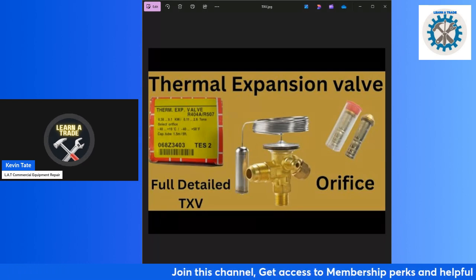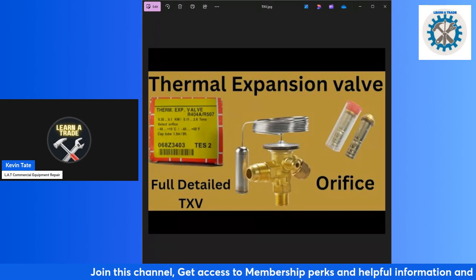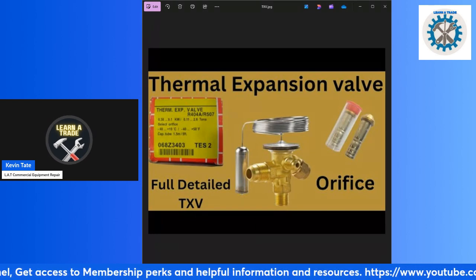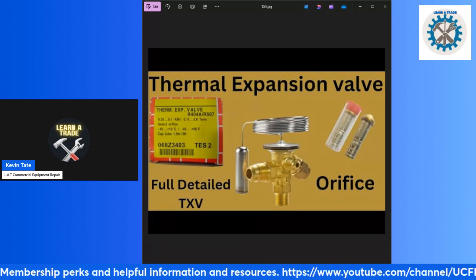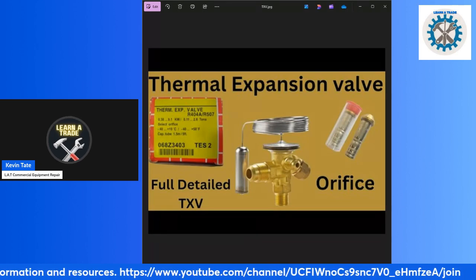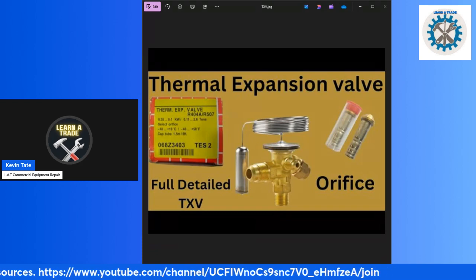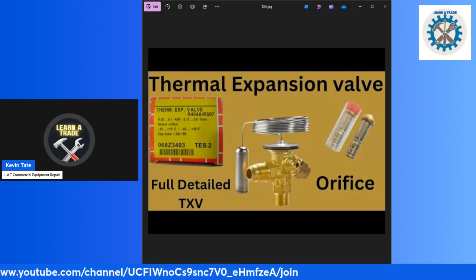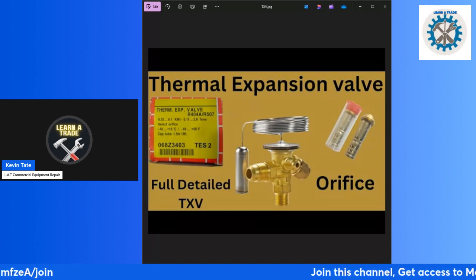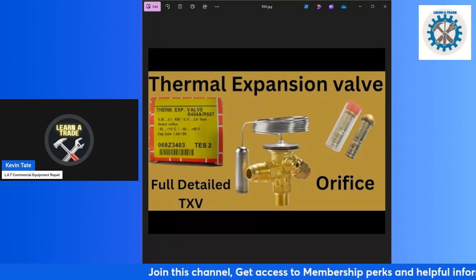Then go to the left to select the nominal tonnage rated valve. That's going to be the valve that you're going to select. You may have to recalculate the flow rate in tons using the liquid correction factor table if the actual liquid temperature is different from 100 degrees Fahrenheit used as the standard rating point.